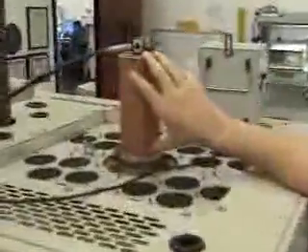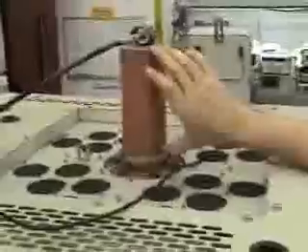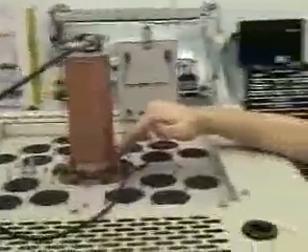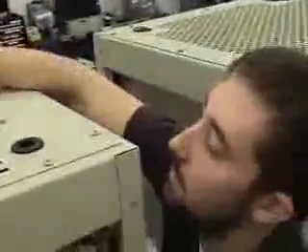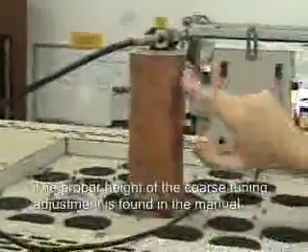This is the coarse tuning adjustment — I think it's the biggest thing that's forgotten about. When we ship this, we have to push it all the way down because the transmitter will be too tall for shipping. So when you install the transmitter or just checking on things, make sure this is at the right height. The transmitter will not tune, will not work, without this being at the right height.